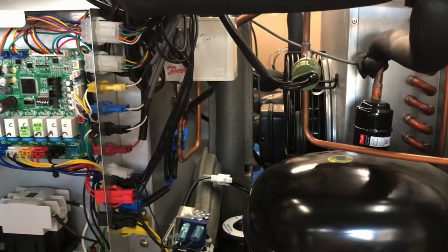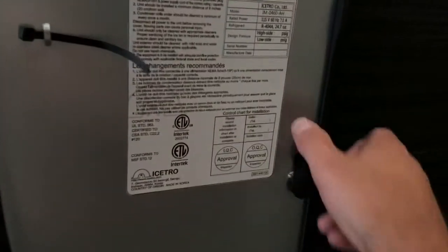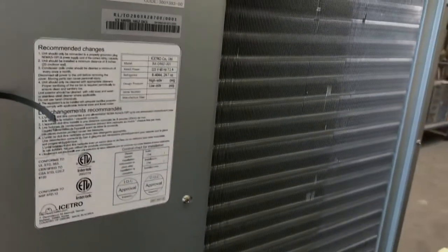But on an ice machine, you'd come out and look at this air filter, and it would be so dirty you could literally peel it off. It'd be like peeling lint off of your dryer vent. When you pull the screen out of your dryer and take all the lint off, that's what it would look like, because no one ever looks at this stuff. When you go into a restaurant and look at an ice machine, no one's ever doing the maintenance. This is just magnetized on there.